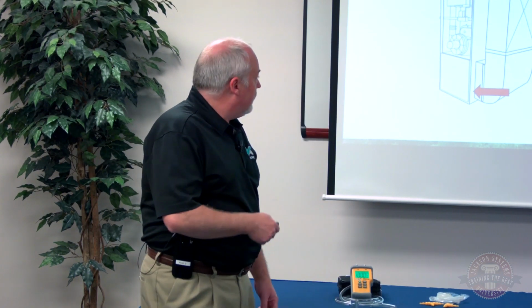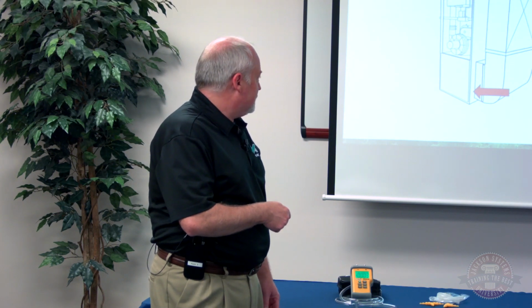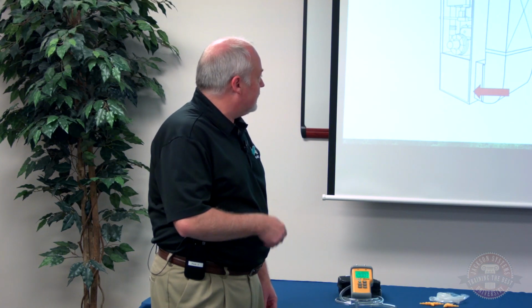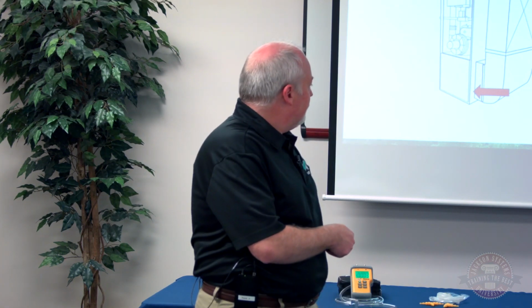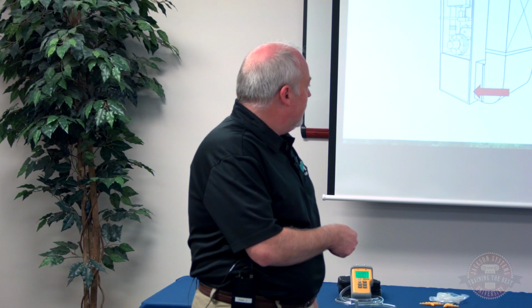Okay. And as I mentioned earlier, the EM201B has both a negative and a positive port. So we're going to connect that tip in the return duct to the negative port and the tip in the supply duct to the positive port. That gives us a direct reading of external static pressure, so we don't have to do that math. Okay? If we've got that single port manometer, take the readings separately, disregard the plus and the minus, and just add that total, and that's going to give you your external static pressure. Okay? So let's take a look at a couple of examples.